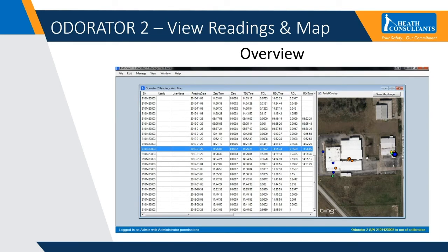Typically, once connected, the data is imported only into the instrument for further processing. It can also be imported and saved to file, which immediately jumps to the create a file type dialog. But a typical sequence is just to import the readings and the periodic fix data alone, and then view readings and map.